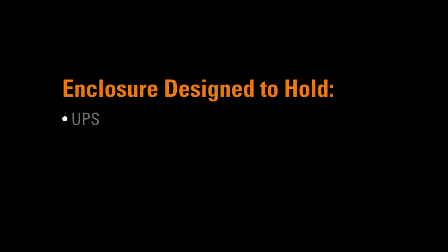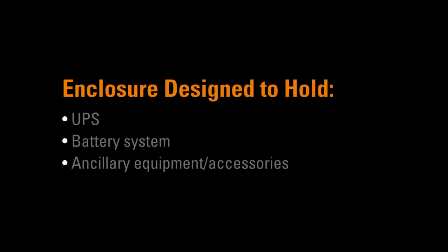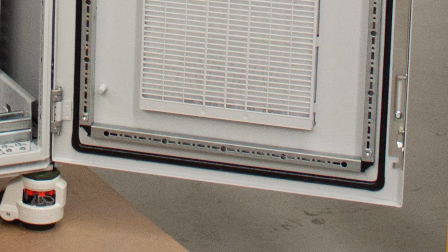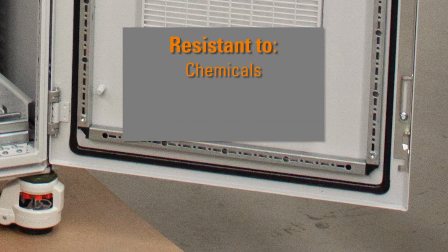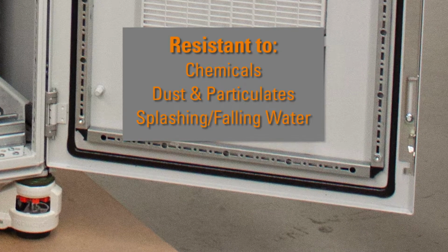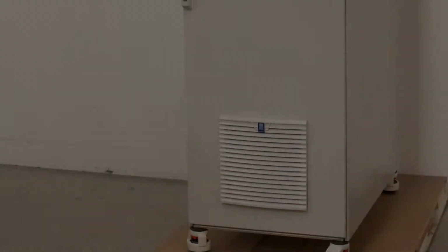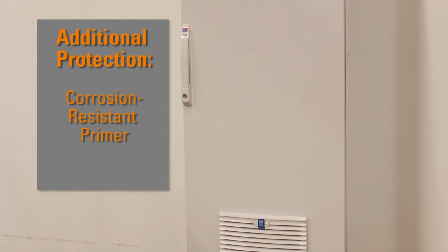Our team started this project with a custom, frame-based NEMA 12 sealed enclosure with a 3,000-pound dynamic load rating, which was designed to house a UPS, battery system, and all other necessary ancillary equipment and accessories. The fully sealed, gasketed enclosure is resistant to chemicals, dust and particulates, splashing, and falling water. The enclosure was also protected by corrosion-resistant primer and powder coating.